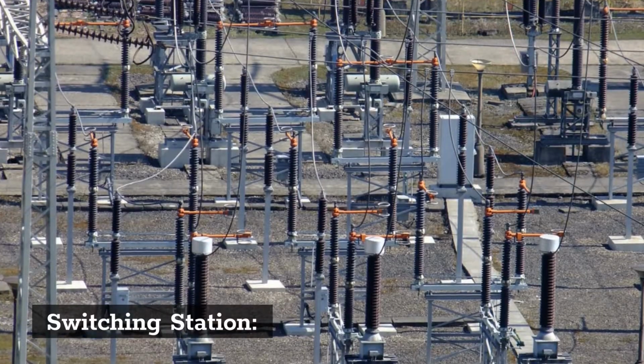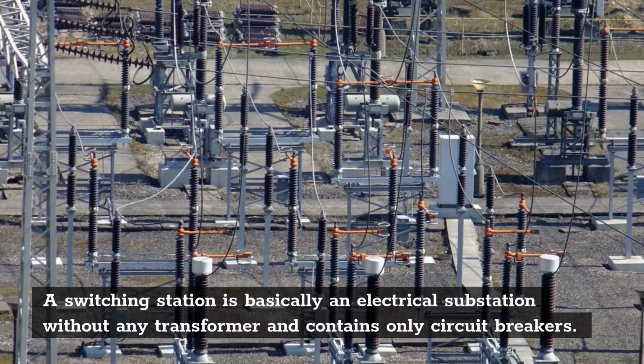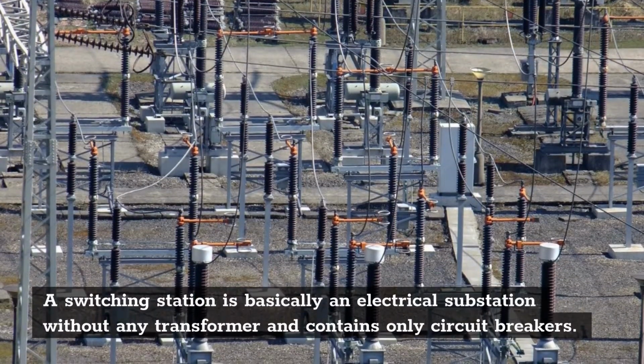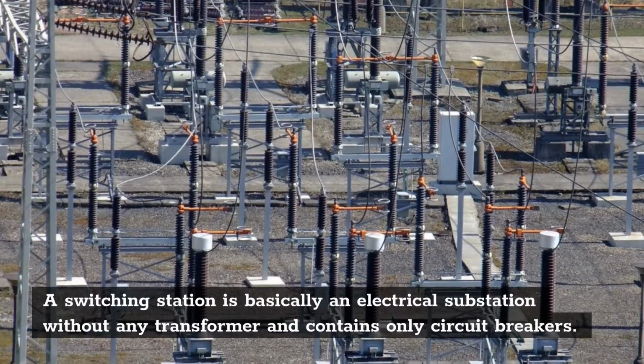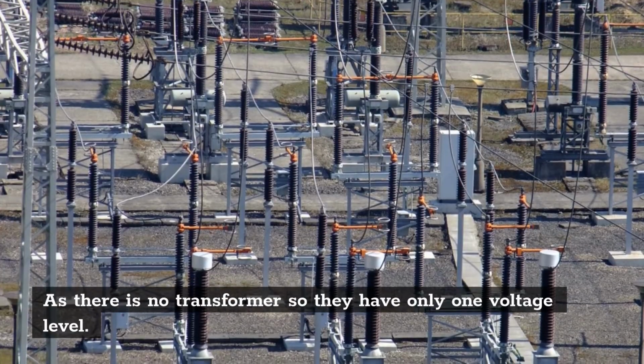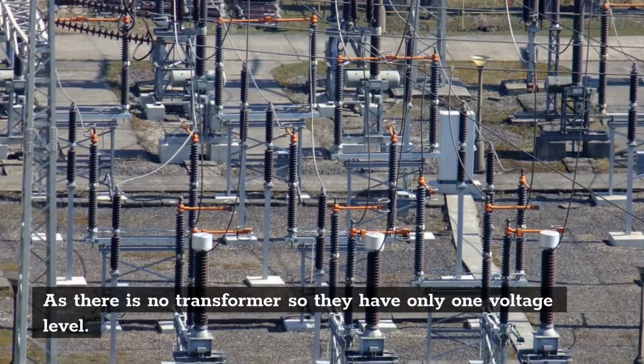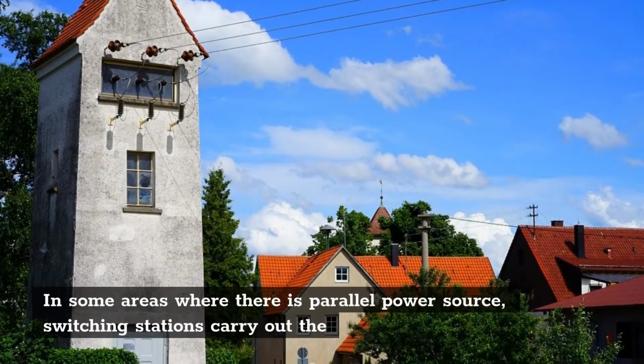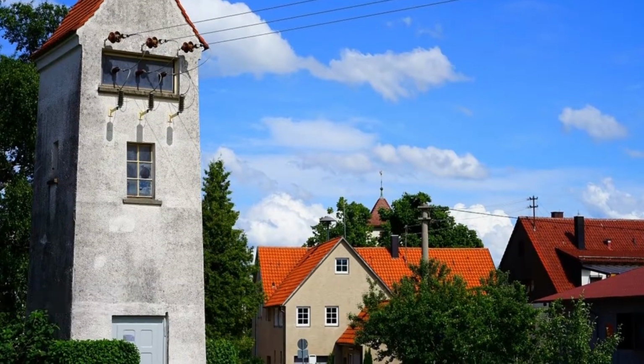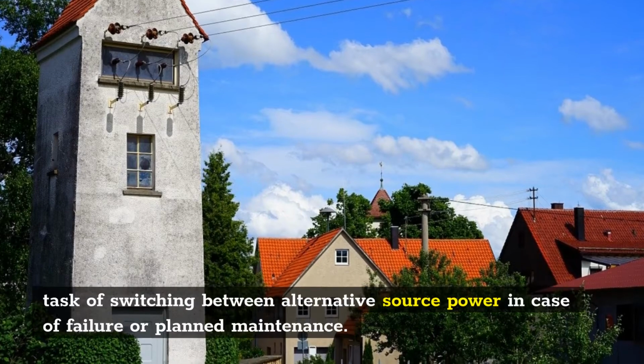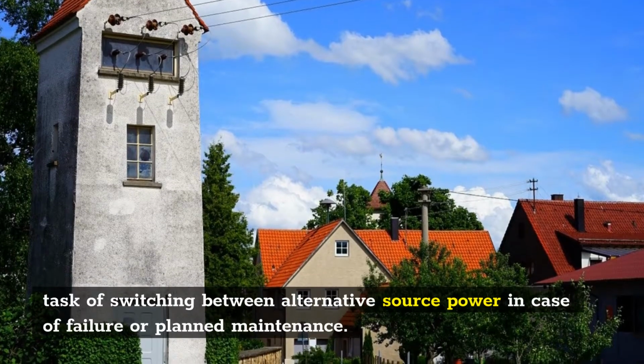Switching station. A switching station is basically an electrical substation without any transformer and contains only circuit breakers. As there is no transformer, they have only one voltage level. In some areas where there is a parallel power source, switching stations carry out the task of switching between alternative source power in case of failure or planned maintenance.